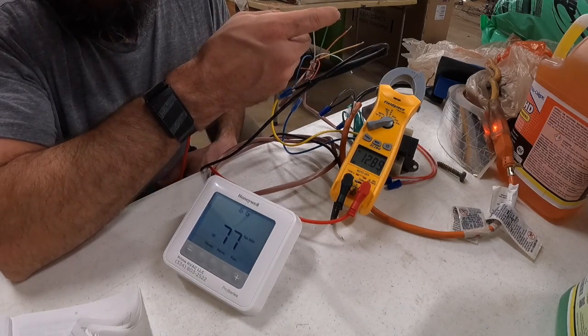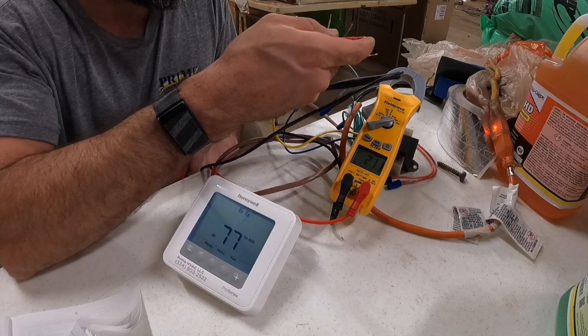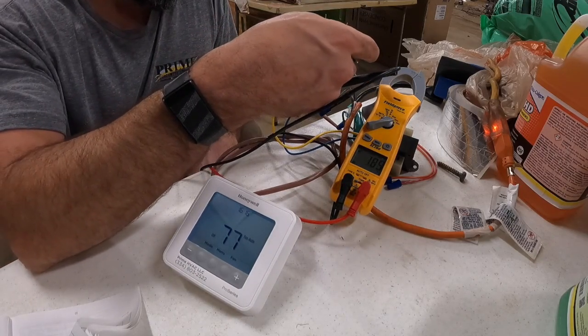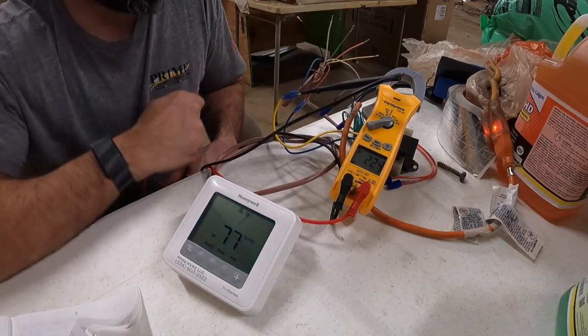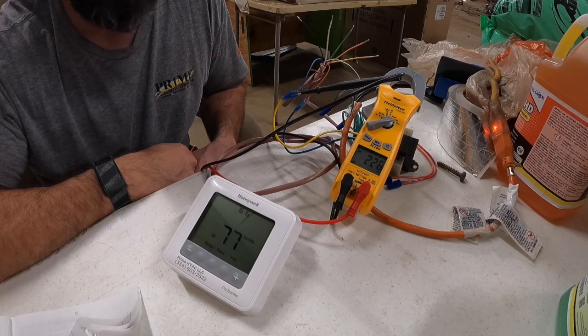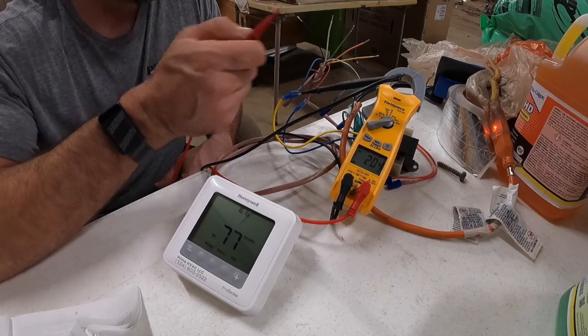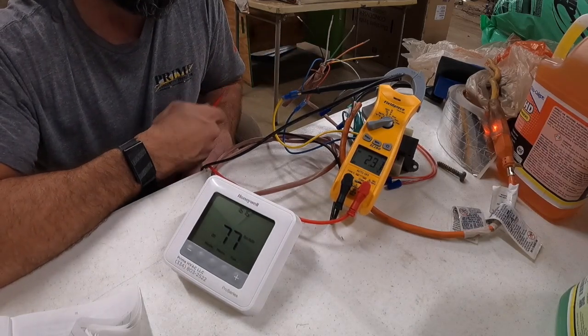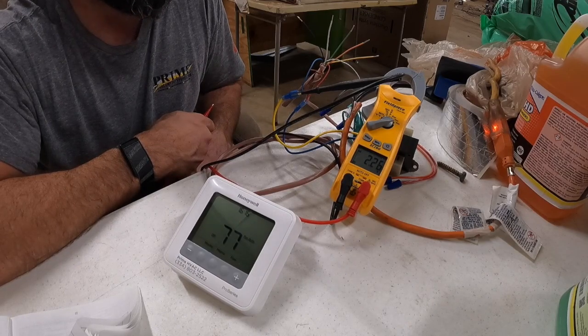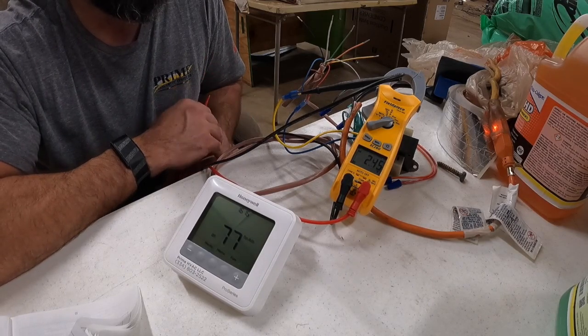16, 16. We're looking for 24. I think we don't have this transformer grounded. We're getting some voltage feeding through onto some of the other wires, but basically this thermostat is not sending voltage through any of these wires, 24 volts, which is what's required to activate the contactors or relays and whatnot that they're going to. So we're going to call for fan on.